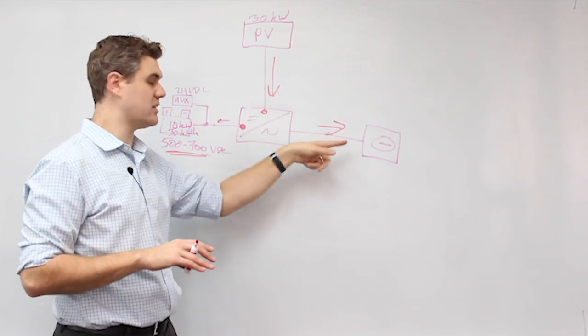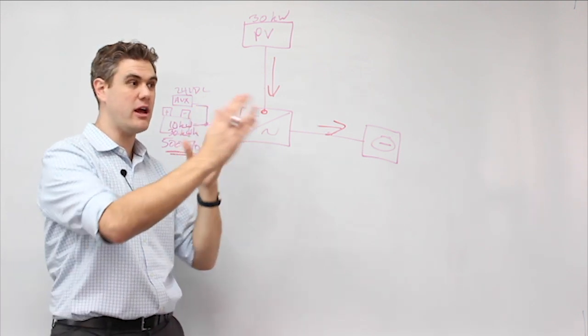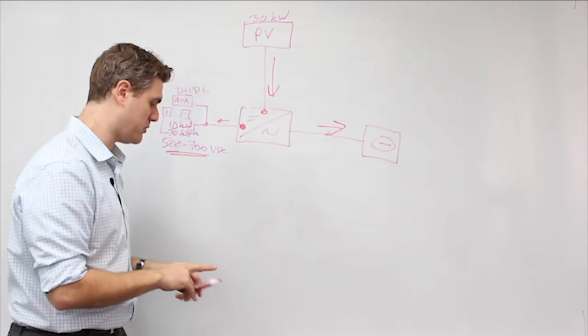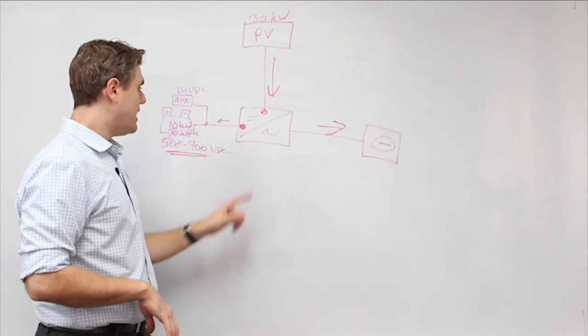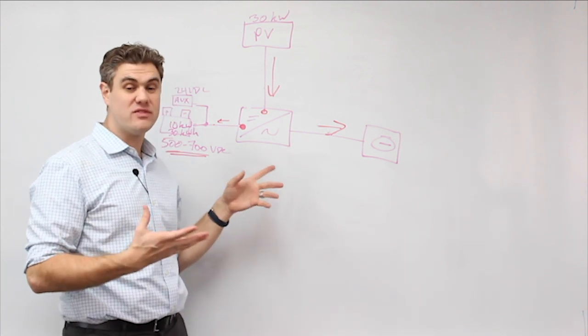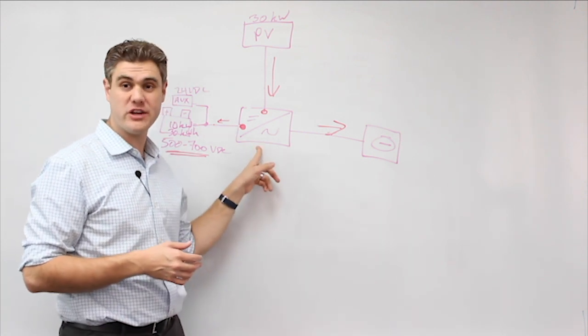It's controlled by one inverter that can see everything. It can see the solar, it can see the grid, and it can see the battery and all the directional power flows between each port. This is relatively easy to do with a minor firmware adjustment in the inverter.